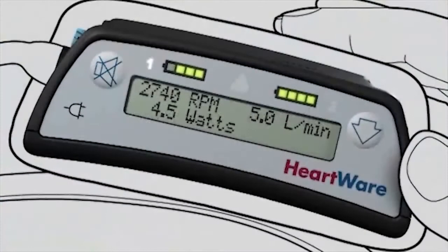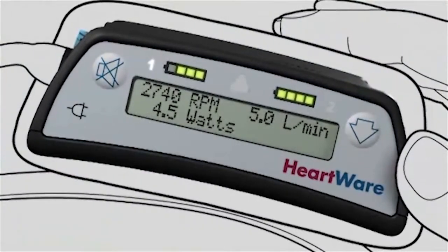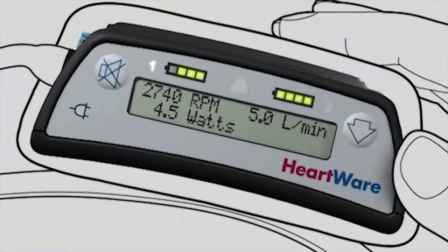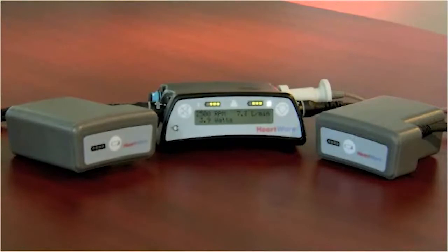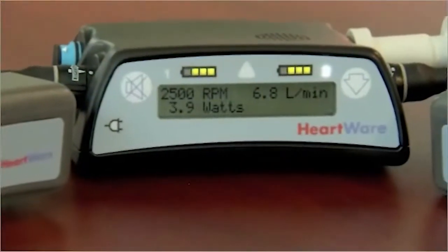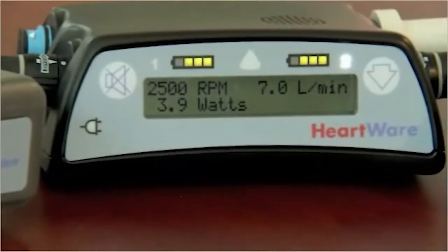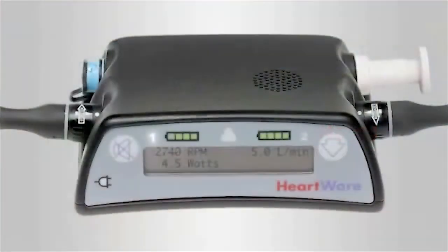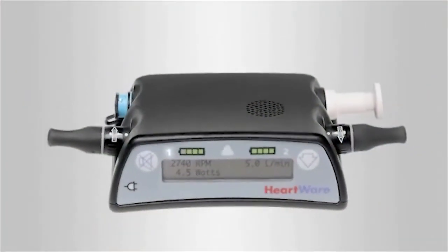The HeartWare controller operates the pump and makes sure that it is working correctly. The display on the controller provides you with information about the pump performance that includes the blood flow, the speed, and the amount of power being used. Also on the face of the controller are two additional buttons. The scroll button, which allows you to toggle between information on the controller, and the alarm mute button. The alarm mute button will mute all low and medium priority alarms.